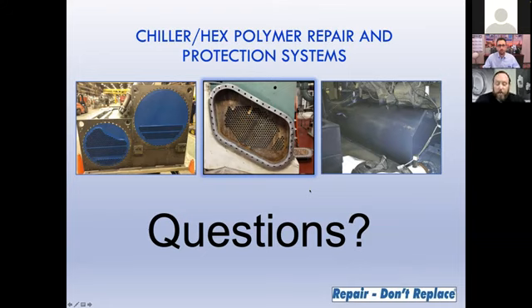The first one that a couple of people had was, how long does a typical repair like this take? When you're doing it start to finish, a chiller repair, can you give an estimate as to how much downtime a customer can expect? Well, that's a good question. Oftentimes we really rely on how quickly the customer needs the equipment back in service. It also depends on the size of the heat exchanger that we're actually coating, if we're talking about a high build system. If we have a standard chiller, say 48-inch to 60-inch diameter, we typically have that chiller completed in 3 to 5 days, depending on the needs of the customer, how many guys we're going to put on the job, or if it's something that needs multiple crews over a couple of shifts a day. So really, it's up to the customer. We try to work within their parameters, but 3 to 5 days is pretty typical.